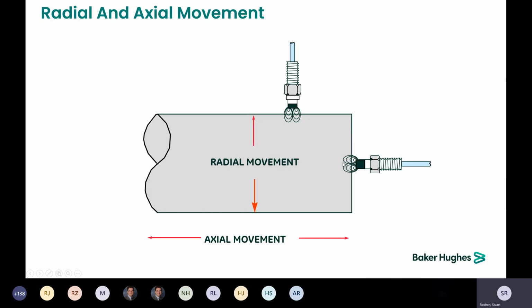These signals can also be read as vibration. I have run into cases where there was axial vibration in a machine and we just jumpered the thrust probes over to a radial vibration channel pair and were able to see how much axial vibration they were getting and help them diagnose what was going on.